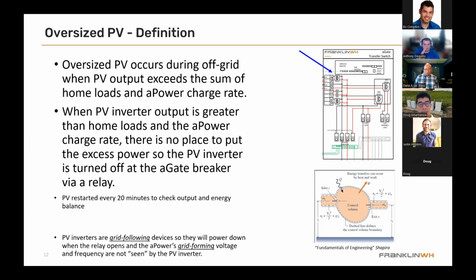So again, we're referring to AC sizing. What that means is if your system hits 8 kilowatts in the middle of the day on a single battery, we're going to shut the PV off so it doesn't overcharge the system. Does that make sense?